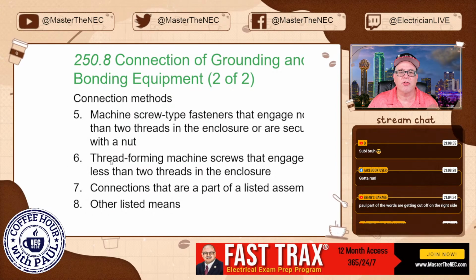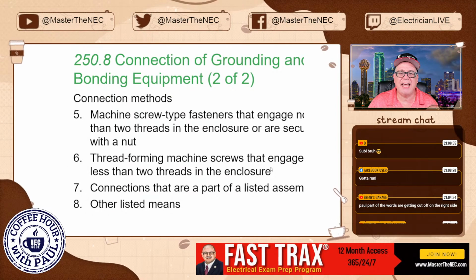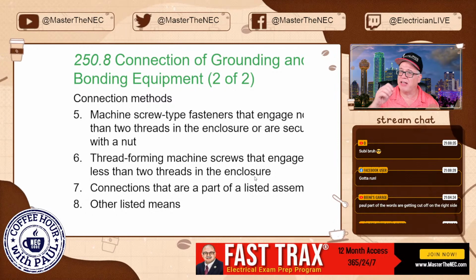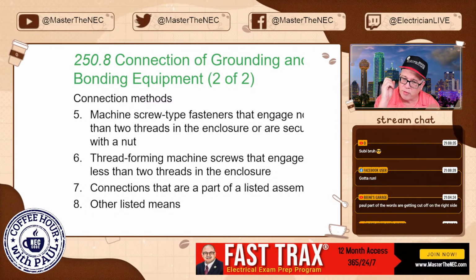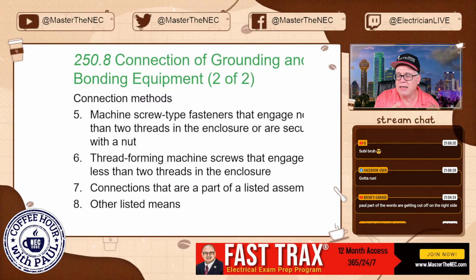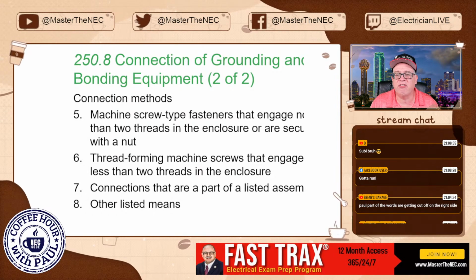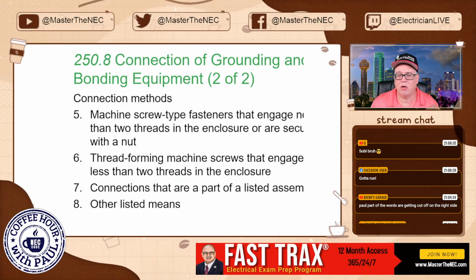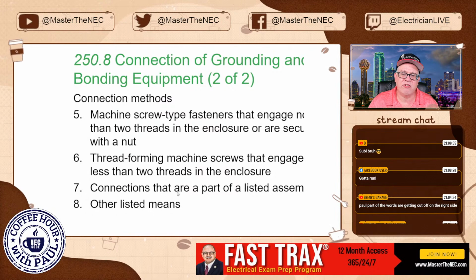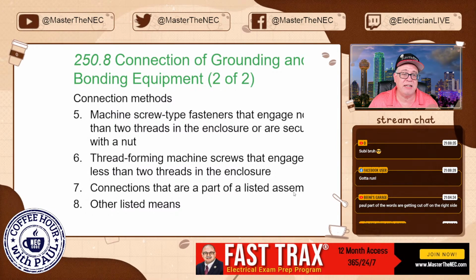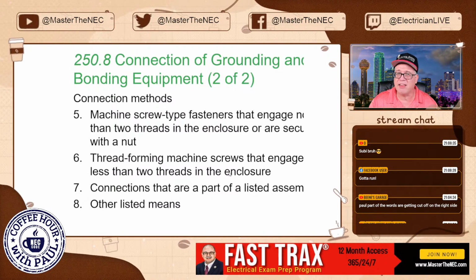Number 6, thread forming screws that engage not less than 2 threads. So these are screws that make their own threads. They form their own machine screw threads, okay? And they still have to engage at least 2 threads into the enclosure if you're going to use them. Connections that are part of listed assemblies might be part of or integrated into the assembly.